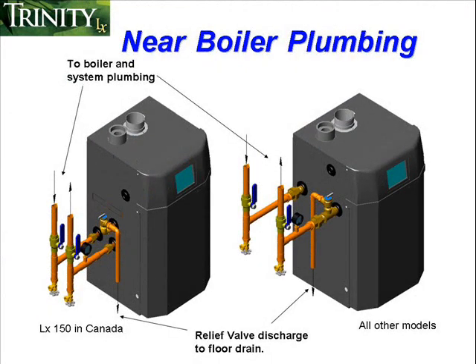When looking at the near boiler plumbing, let's start with the pressure relief valve. A 30 psi pressure relief valve is factory supplied with all Trinity Lx boilers. Models that are dual certified as either boilers or water heaters also include an additional higher pressure relief valve of either 125 psi or 150 psi depending on the model. Excluding LX150s that are sold in Canada, Trinity Lx boilers have a maximum allowable operating pressure of either 145 psi or 160 psi depending on the model.